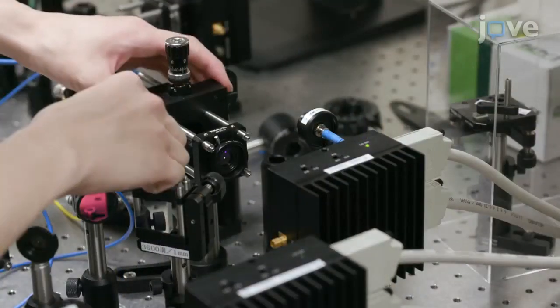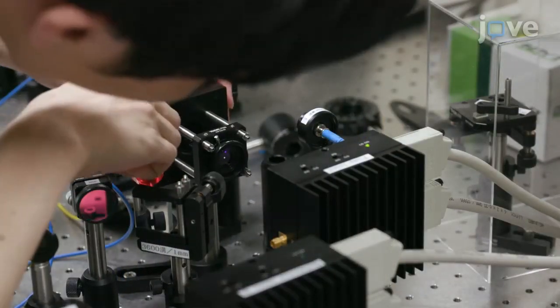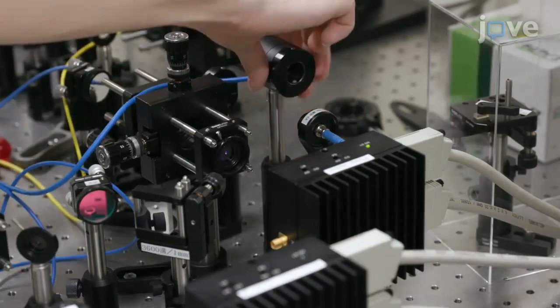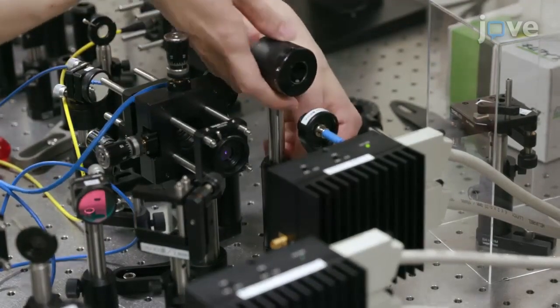Next, couple the laser to a polarization-maintaining optical fiber. Direct the fiber to a power meter and adjust the coupler screws to maximize the output power.